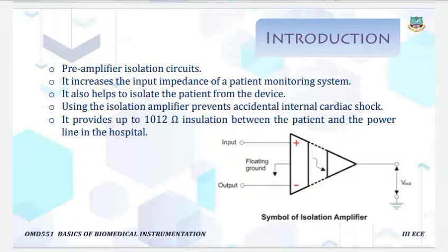It provides up to 10 power 12 ohm insulation between the patient and the power line in the hospital.